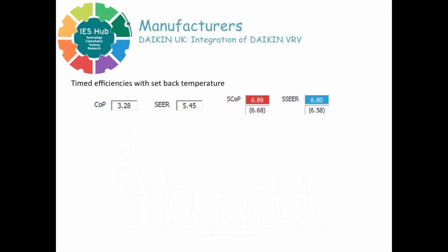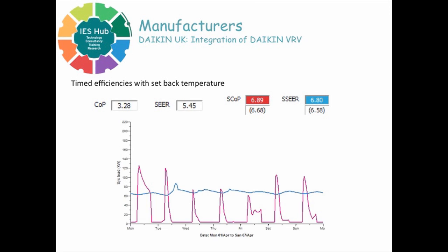Okay, some other discoveries that we've had. Leaving the systems on. You turn a system off, what happens to the temperature? It changes. If you leave the system on, you maintain a temperature within the space. This is just some output details here from design that we looked at a server room. Again, we were looking for heat recovery efficiency within the space.